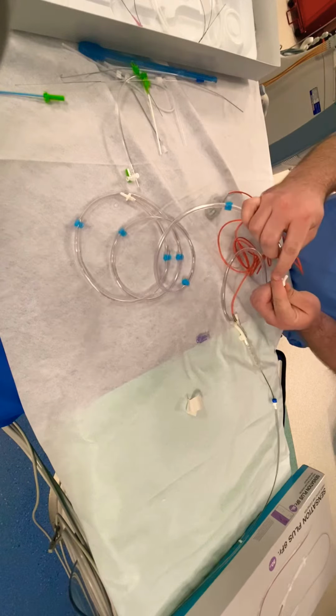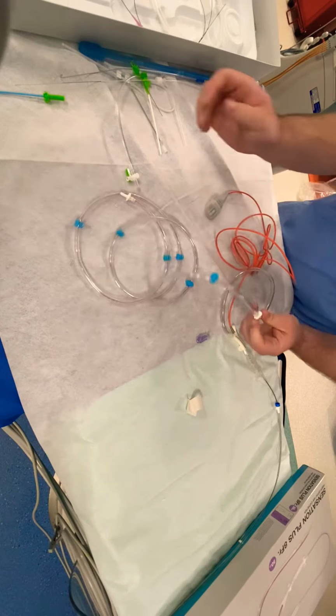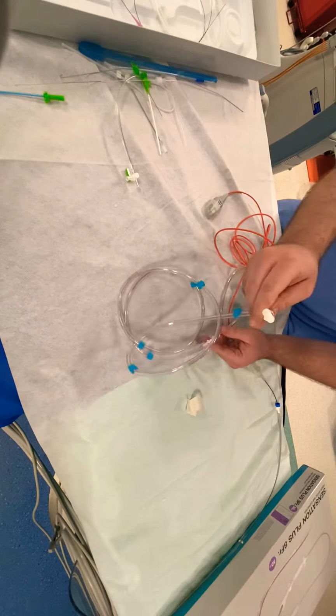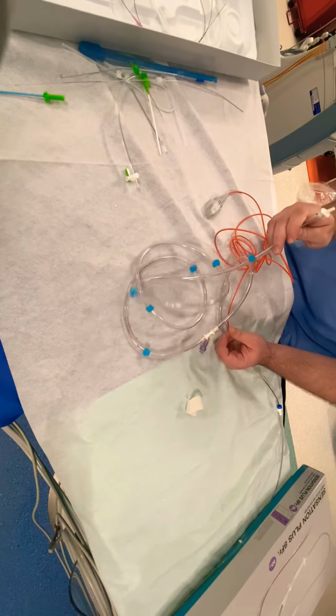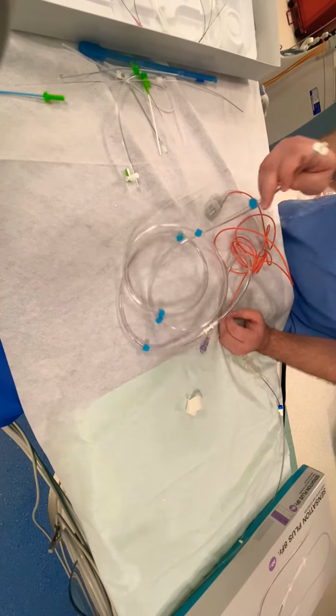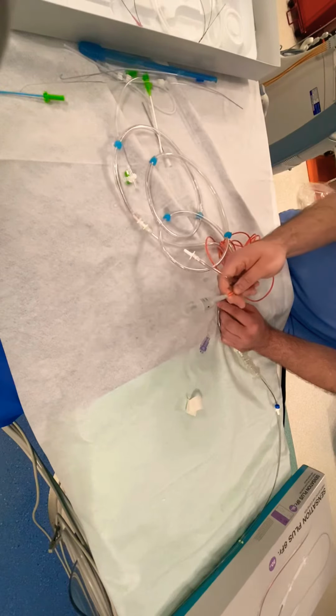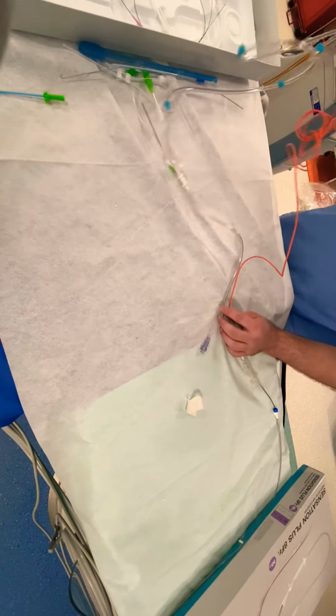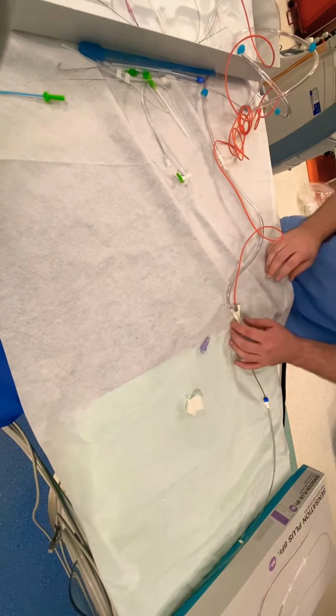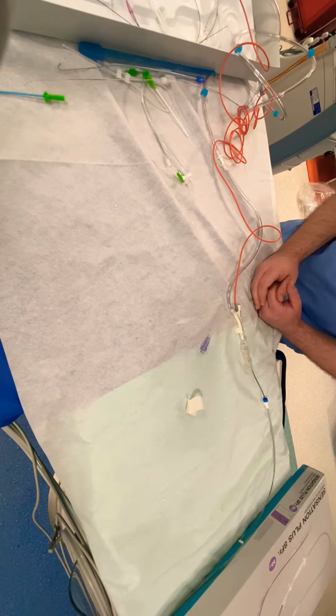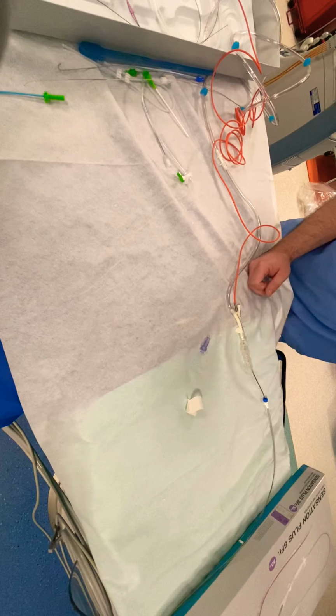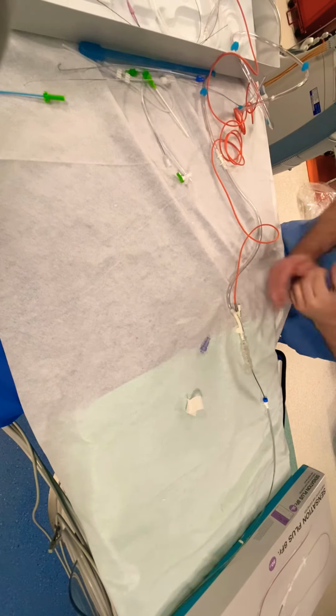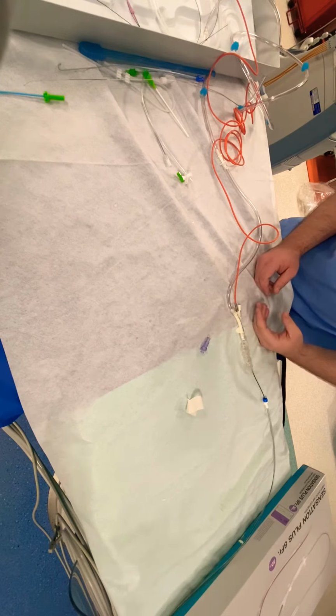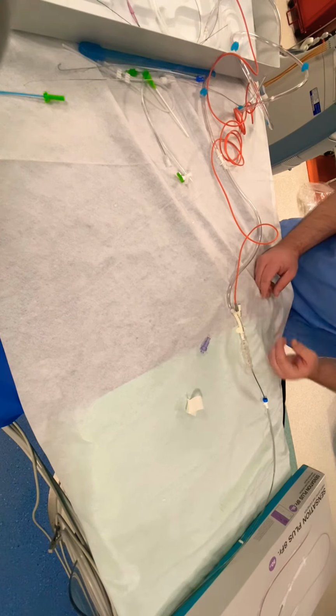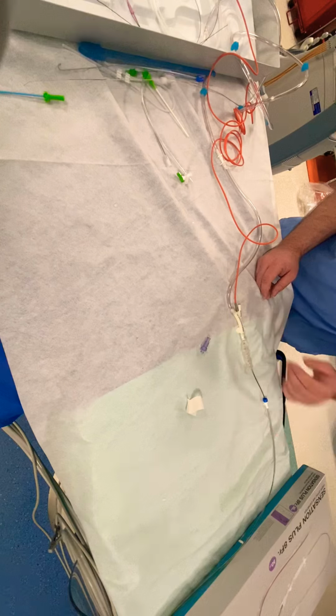You hopefully heard that vacuum that was pulled on there. That connection will go on there. This slip tip goes over to the, you'll see that connection in a moment on the back of the balloon pump. So both of these will get handed off to your circulators, okay? Once they are connected, your balloon is okay to turn on. There's a start button. It does take 45, 50 seconds or something like that. It does this initial calibration. It zeroes automatically, and it does that by the fiber optic cable, which goes to the end of the balloon.